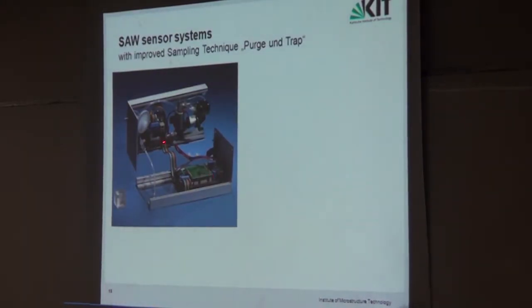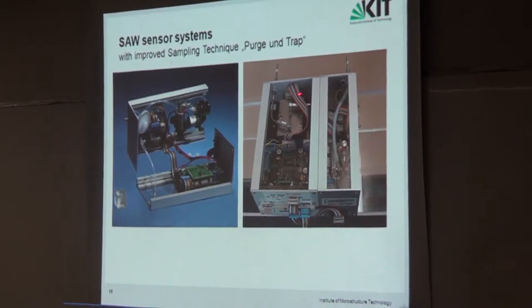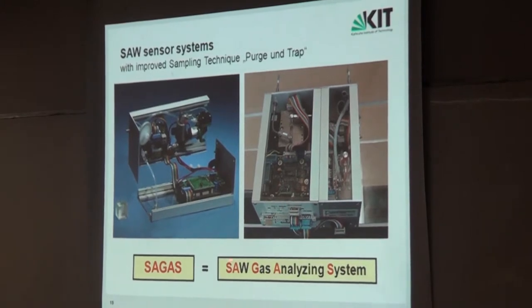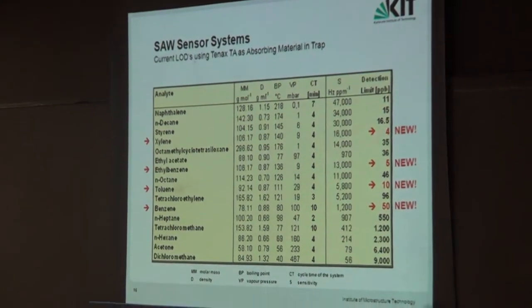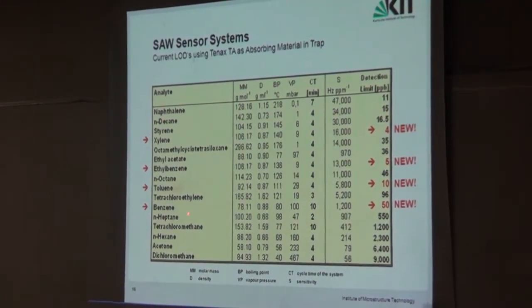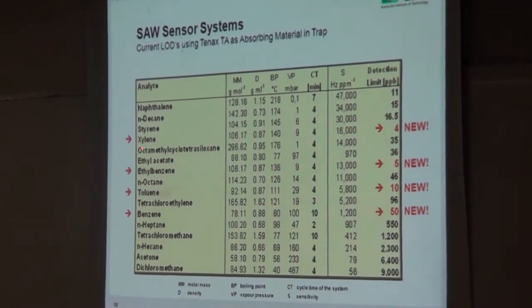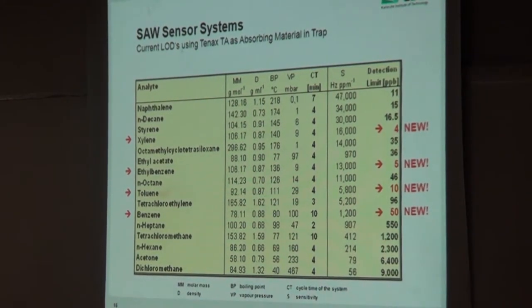The trap system — which you can see in Mauro's lab — is the complete system opened up: the sensor head with eight sensors, data electronics, and the add-on pre-concentrator module. We call it SAGAS — Surface Acoustic Wave Gas Analyzing system. Here is a list of different analytes tested over the years with their sensitivities and limits of detection, reaching the PPB level for several important compounds as required by industry.